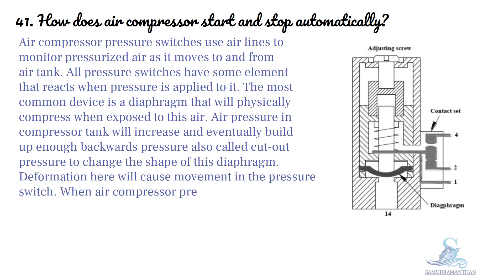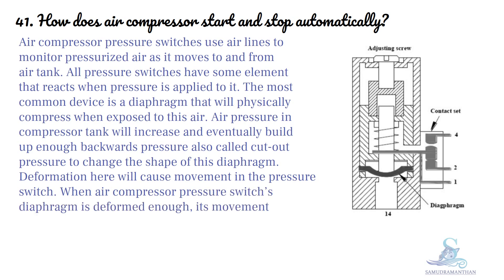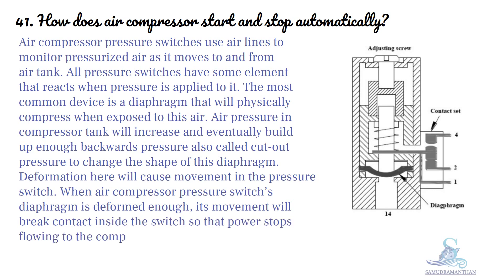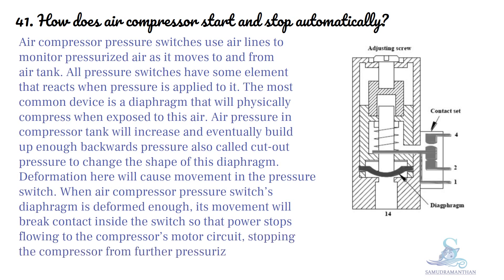When the air compressor pressure switch's diaphragm is deformed enough, its movement will break contact inside the switch so that power stops flowing in the compressor's motor circuit, stopping the compressor from further pressurizing the air in the tank.